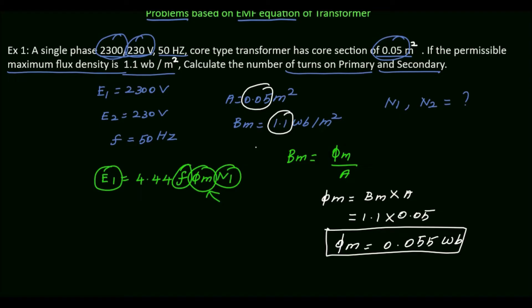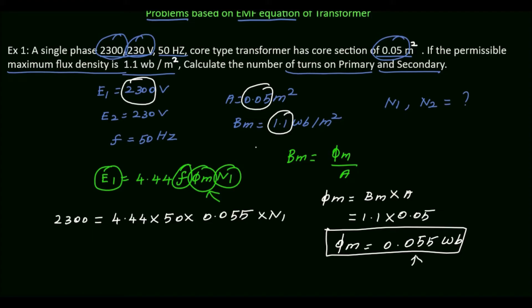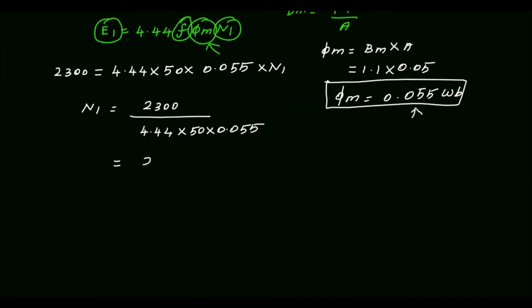Now we calculate the number of turns N1. Substituting into the EMF equation: E1 = 4.44 × F × φM × N1, so 2300 = 4.44 × 50 × 0.055 × N1. Therefore N1 = 2300 ÷ (4.44 × 50 × 0.055) = 2300 ÷ 12.21, which gives approximately 188.37.